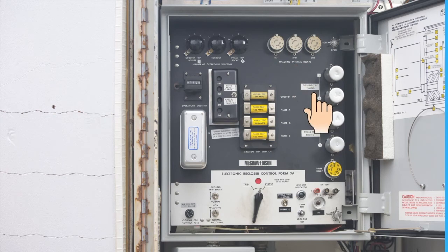Ground fault sensing and tripping operations occur exactly the same as phase fault sensing and tripping, except that zero sequence ground current is sensed instead of phase current. The ground fault circuitry includes its own minimum trip resistor, fast and delayed trip timing plugs, and number of fast operations setting. Reclose and reset intervals and operations to lock out are common for both phase trip and ground trip modes of operation. There is a handle to open and close the recloser.